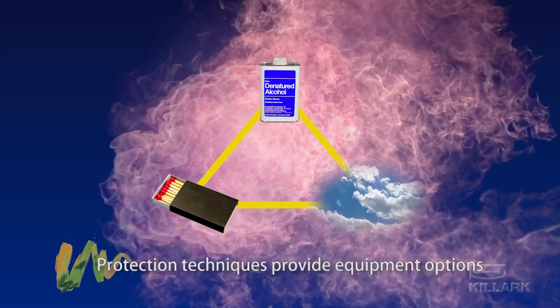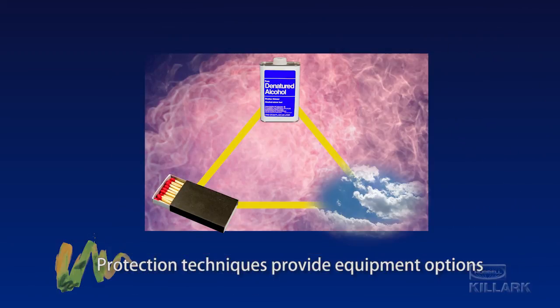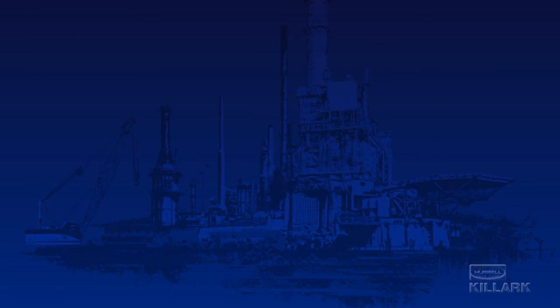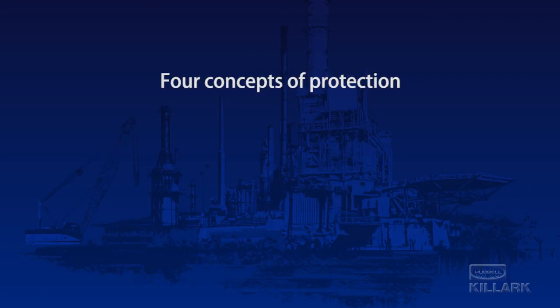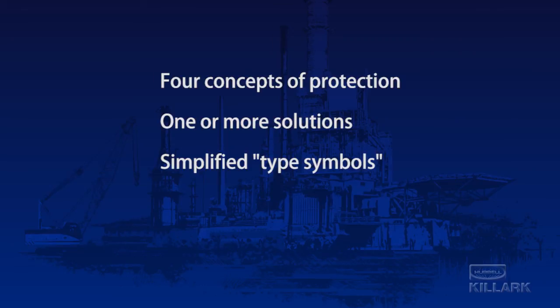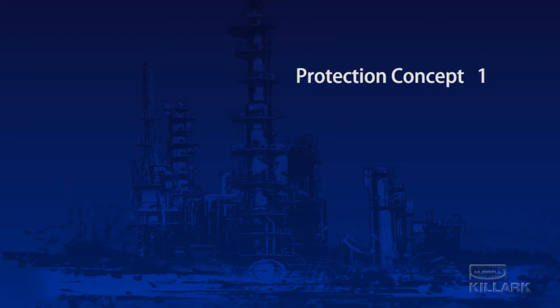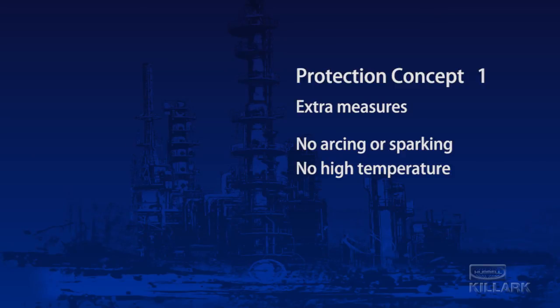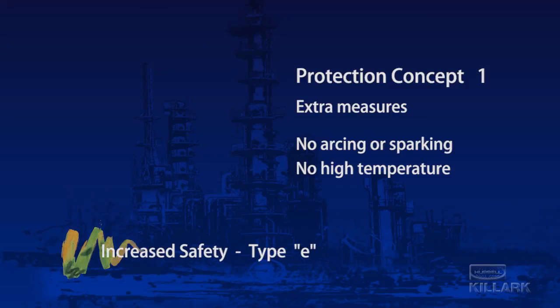The range of protection techniques can restrict the presence of the combustible mixture, isolate or reduce the energy of the source of ignition, or safely contain or quench combustion that could be initiated by the electrical device. Within these general approaches, there are 4 basic concepts of protection, each with one or more engineering solutions. The individual solutions have been assigned a simplified type symbol to make identification and specification easier and more consistent. The first concept includes equipment that has been constructed taking extra measures to produce no arcing, sparking, or high temperatures. These are known as increased safety devices, type E.